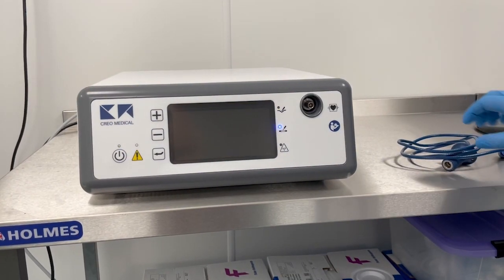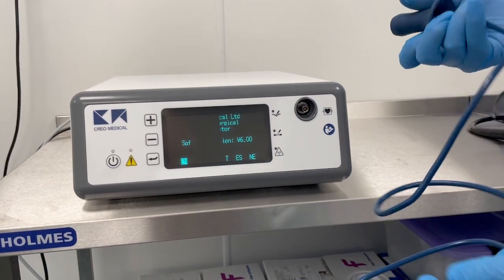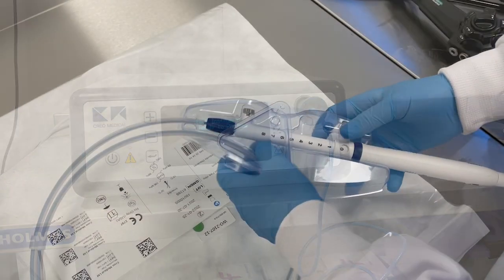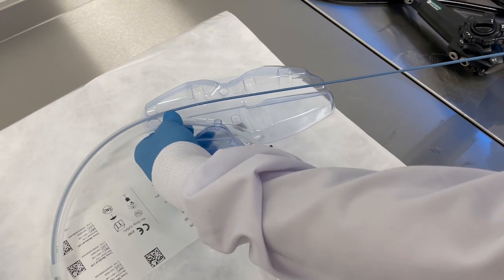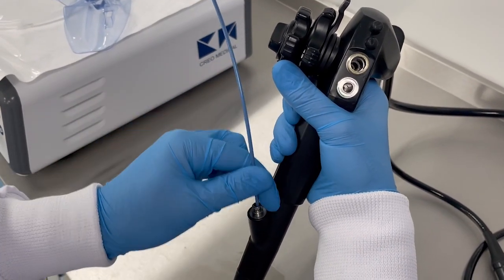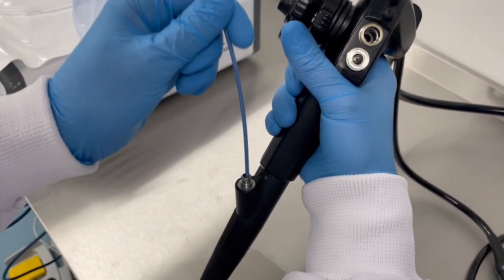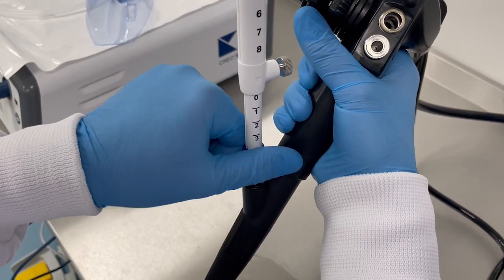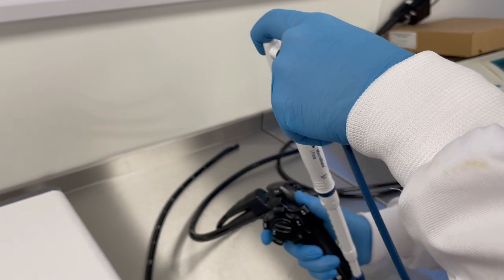Turn on the generator by pressing the power button and wait for instructions to attach the instrument. Insert the interface cable into the generator. Pull the plastic tab to release the handpiece, lift it up and pull it until the catheter is outside of the coil. Insert the catheter into the endoscope working channel and feed it through until the handpiece touches the Luer lock. Twist to the right to secure the handpiece to the endoscope, then attach the interface cable to the handpiece, using your thumb to support the back of the connector.